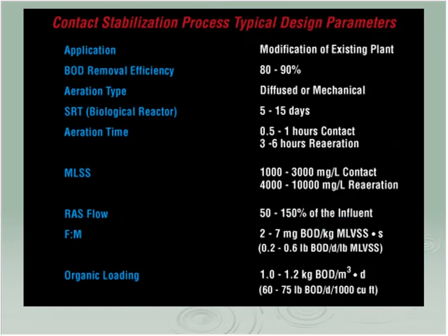And if the engineering firm was nice enough and thoughtful enough, and if your budget was high enough, you folks on computers can't see this, but if I break it down simply, this goes back to a plug flow facility where we come in here, and we come out there. Well, they give me valving so that I could actually send this around and come in here. Actually, it'd be better to come down right here. I'd switch my valve during the rainstorm. I'd come in here. This would be my contact tank, this one short chamber. And then my RAS would come back here, and this would all be re-aeration. By changing your valves, you could change from plug flow into a contact stabilization mode and try to save the plant.